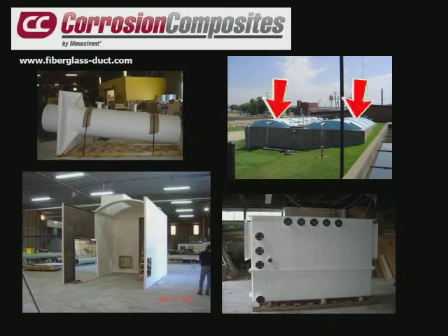The upper right, we have some 20-foot span covers over wastewater tanks, barrel type covers that bolt together. We've done several projects like this. It's for odor control, and it also controls the foam that can build up in the wastewater tanks. That also has a core material, and it is a balsa core for stiffness to keep them light and stiff.